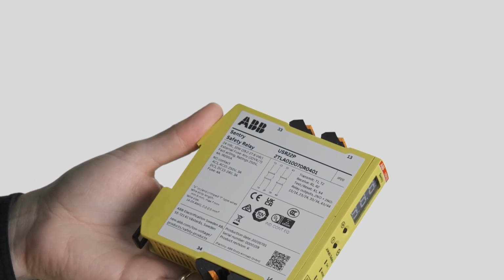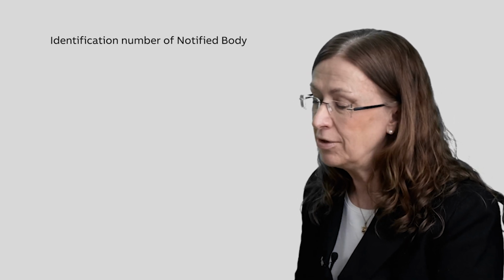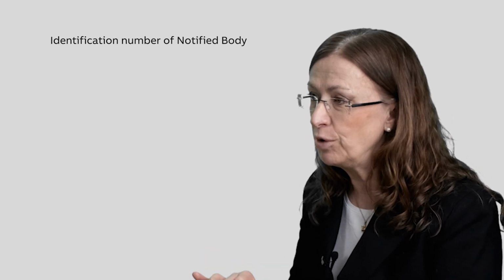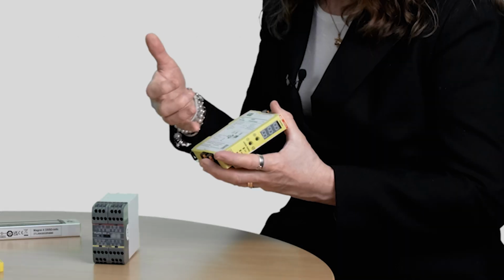If we look at the label here, I can see the CE mark. Are there any changes on that? The CE mark shall look like it does, but since this product has been certified at a notified body, with the machinery regulation we need to add the identification number of that notified body next to the CE mark.